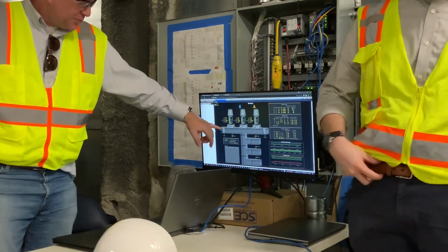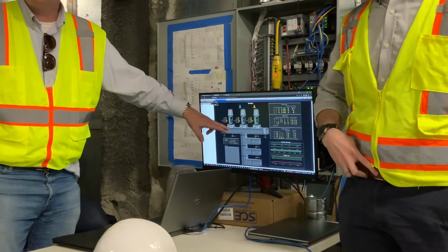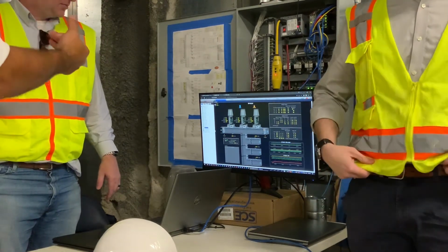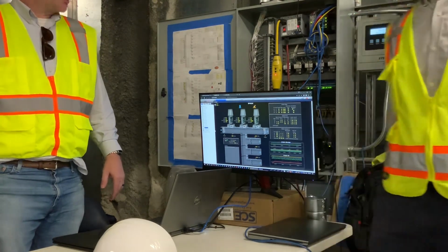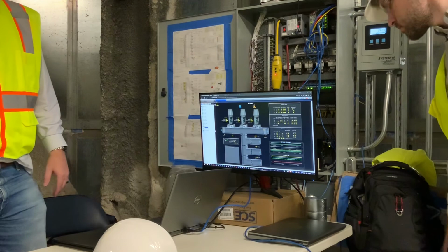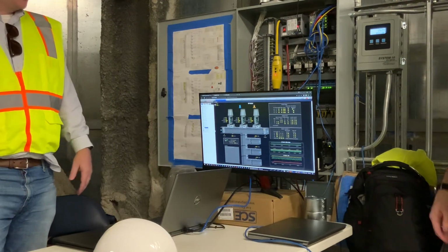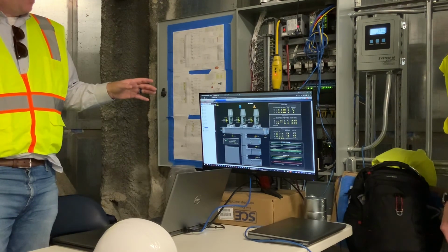Well, for these, these are the bleeds. So these are not a percentage. They're two positions. The reason why I like to send it over there is to tell you sometimes they get stuck open. Feedback. So it doesn't have feedback. Generally, no. Like if you buy a two-position actuator, it's open and closed. Yeah, it's open, closed. So these particulars are.